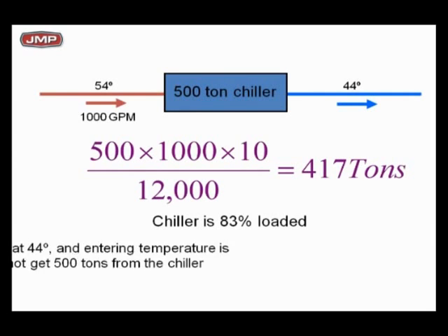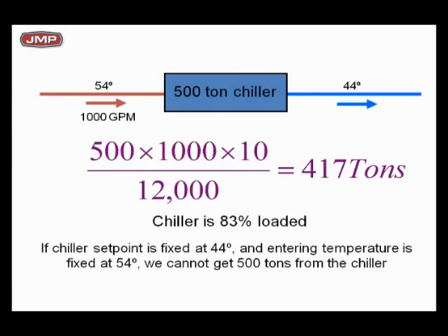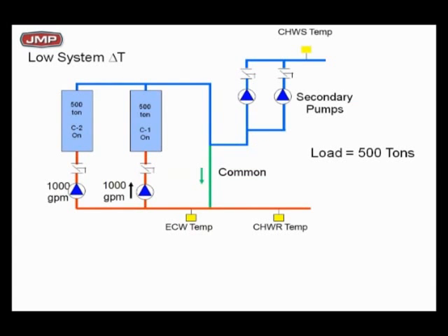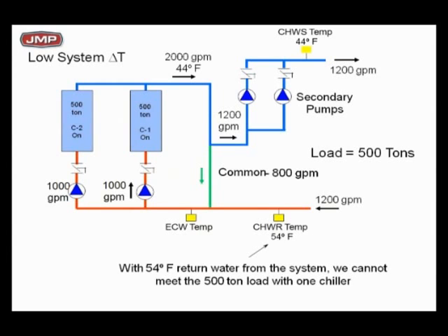This is the part you need to get straight. If the chiller set point is fixed at 44, you can't do it. What are we going to do? This is called low system delta T. We've got that 500-ton load out there. We're producing 2,000 GPM at 44-degree water. I'm taking 1,200 GPM out. I've got 800 GPM on the common pipe, same numbers as before, but look what I've changed. Instead of coming back at 56, I'm coming back at 54. I have low delta T syndrome.